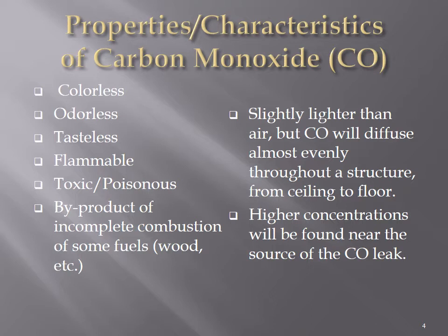One of the characteristics of carbon monoxide is that it's slightly lighter than air, but understand that it's such a minute difference that it's really going to diffuse very evenly throughout a structure from the floor to the ceiling. So anywhere in an enclosed structure where you think carbon monoxide will be, it will be fairly consistent throughout. Although we're going to find higher concentrations near the source of the leak, for example, a gas water heater or a gas heater, and we'll obviously have higher readings as we get closer to that source. But as it goes out into the structure, it's going to be evenly dispersed from floor to ceiling.